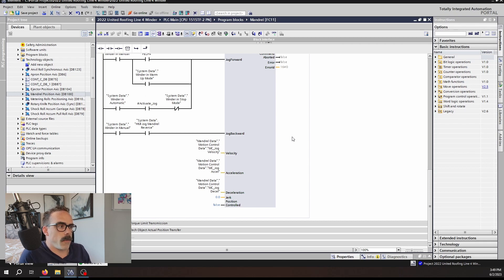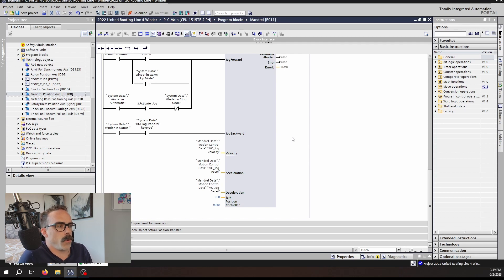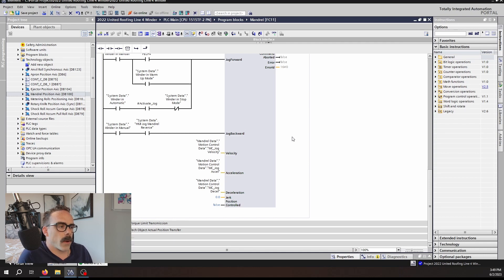Meaning if you have following error monitoring enabled, you can get a following error fault in a velocity move. As you can see here, I've disabled the position controlled move because I don't want to be actually tracking whether or not the speed is exactly how it needs to be.